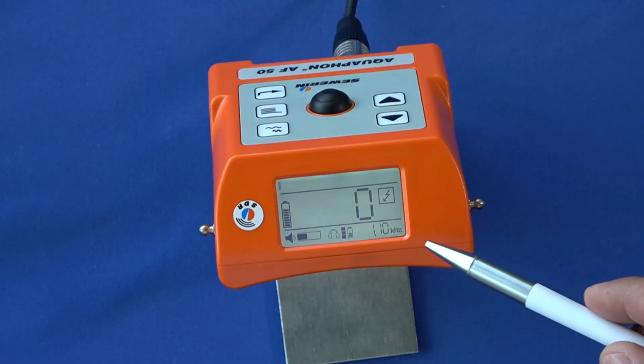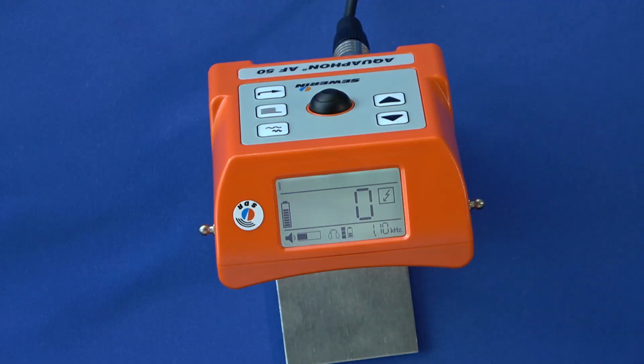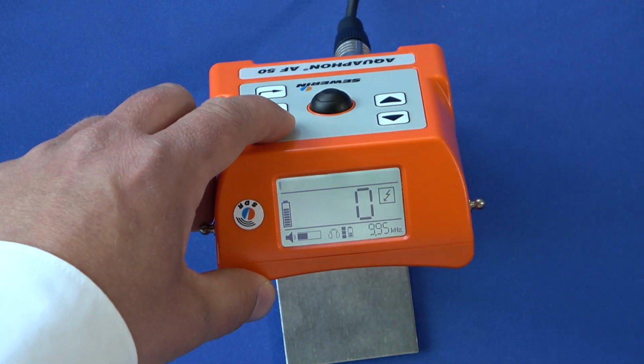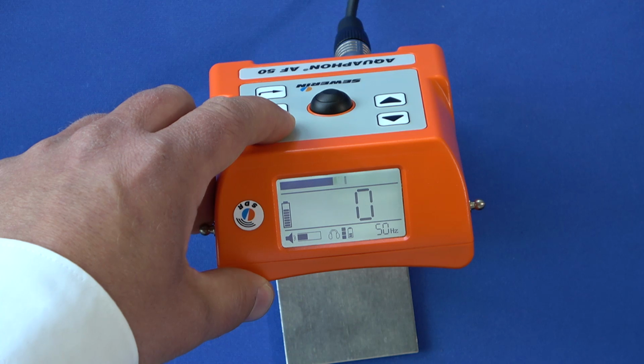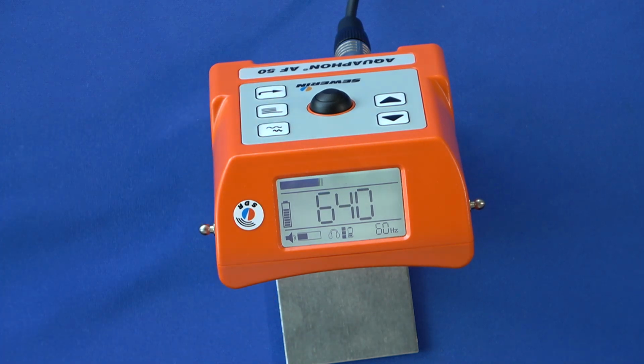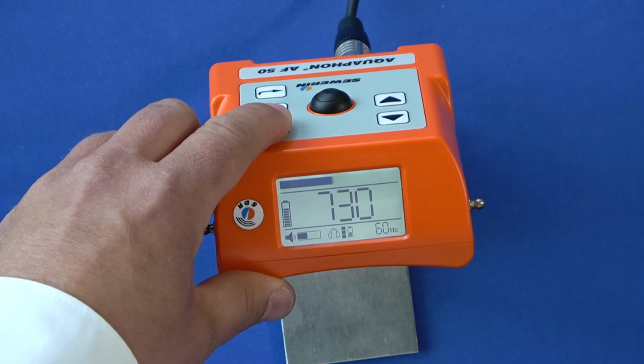At the bottom right, you see the selected location frequency, which can be changed by pressing the filter button. In addition to the 3 active transmission frequencies of the FERROPHON FG50, 2 other frequencies are available. These are used for the passive location of live cables. Adapt the location frequency of the AF50 to the selected transmission frequency of the FERROPHON FG50.